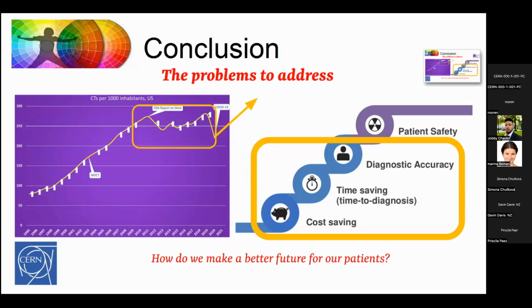So I kind of break a CT scanner up into 4 parts: gantry, tube, detector, and mathematics. In parallel to all this work in detectors, there's been quite a lot of work on the sources. The sources in, you know, like a standard CT like the GE Revolution are huge, they weigh 20, 30 kilograms, 20 amps power input, sort of thing. But with photon counting, you go to lower power, and that enables new sorts of sources.